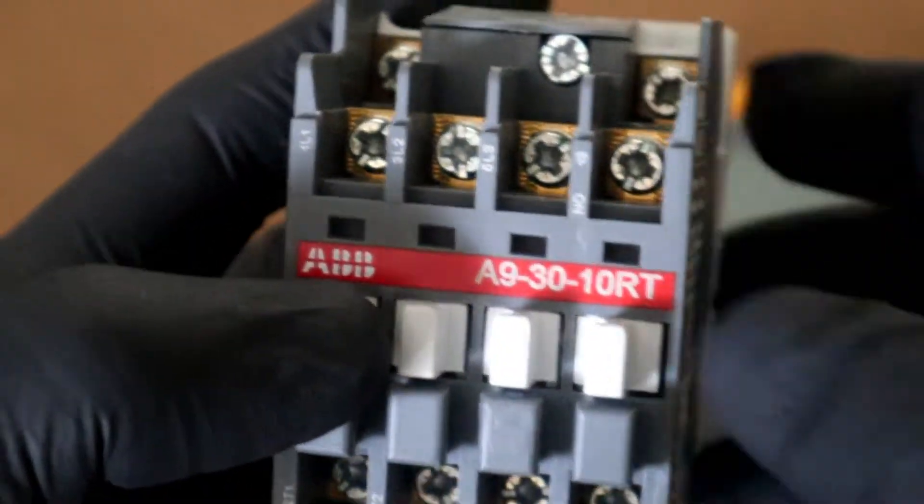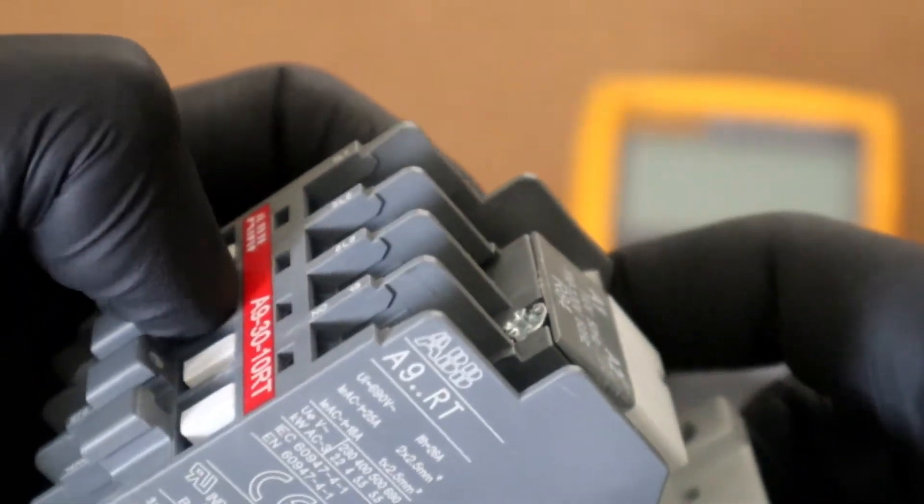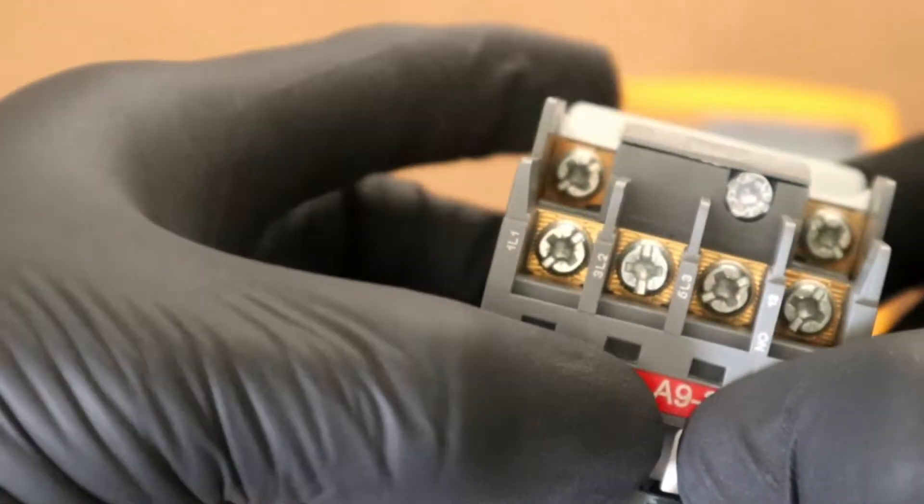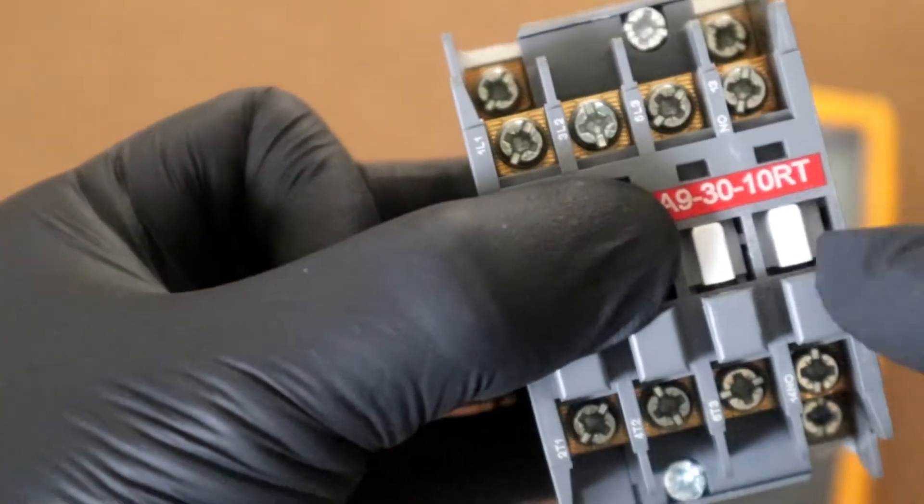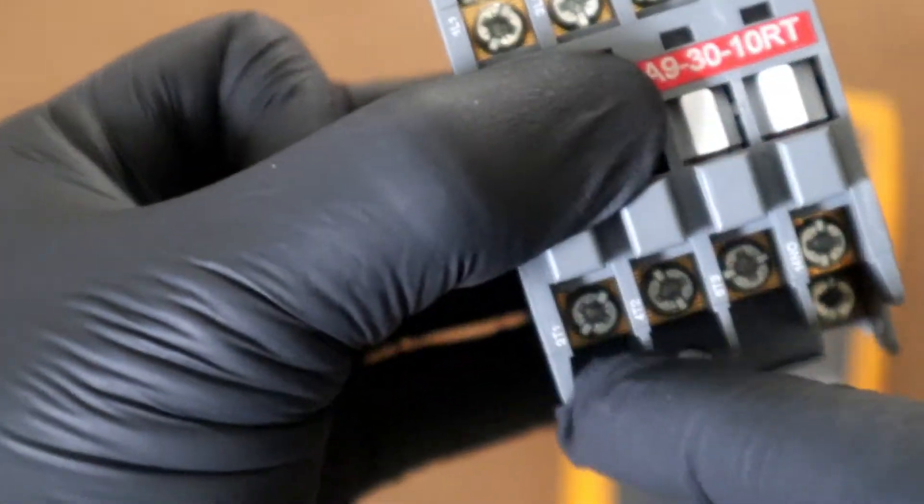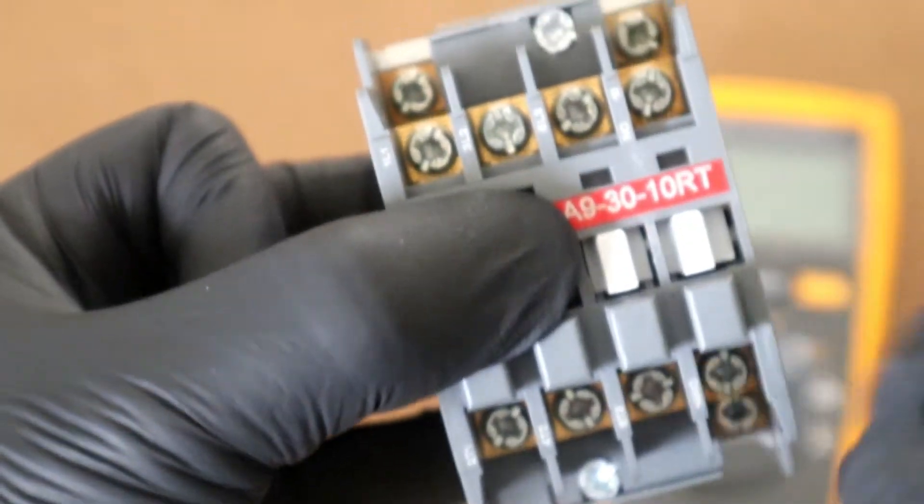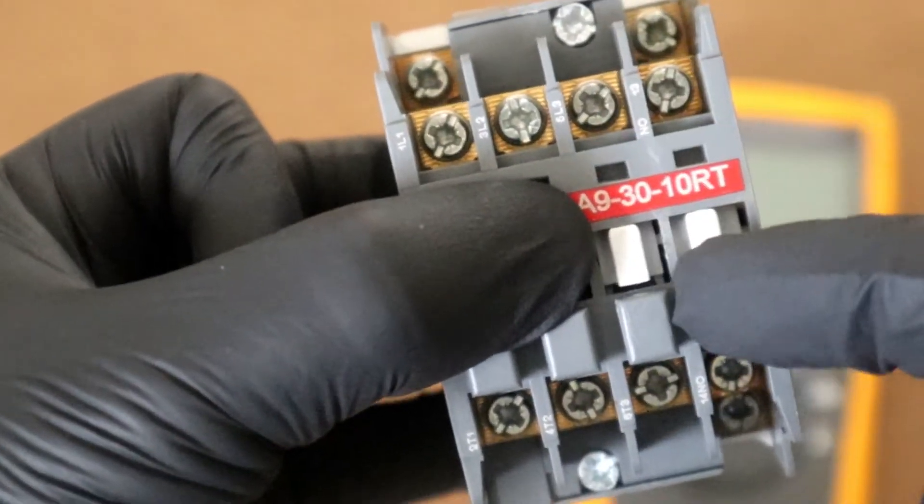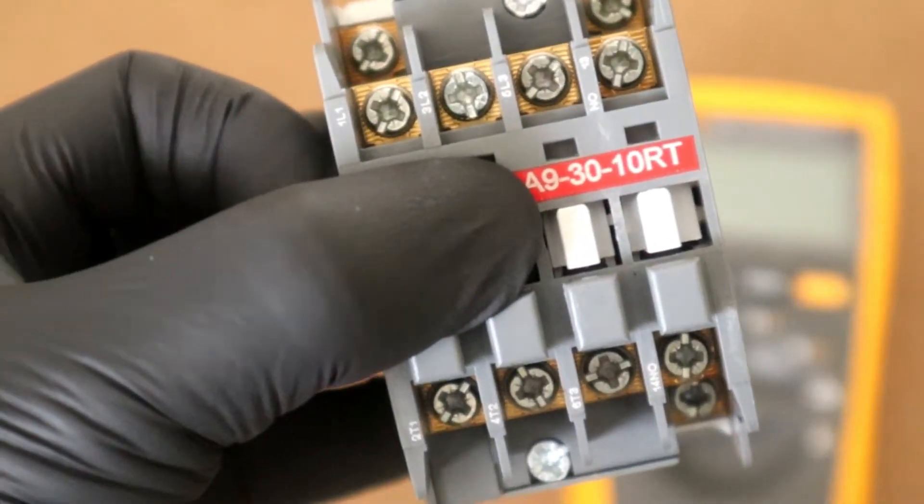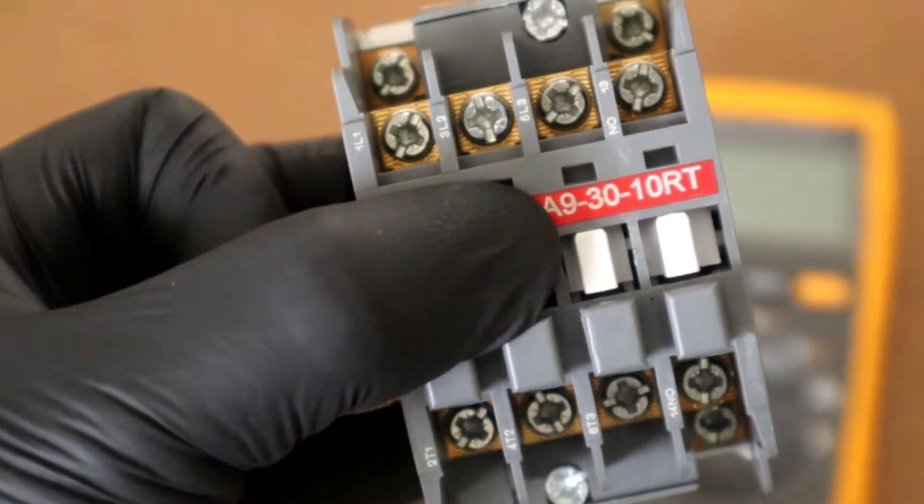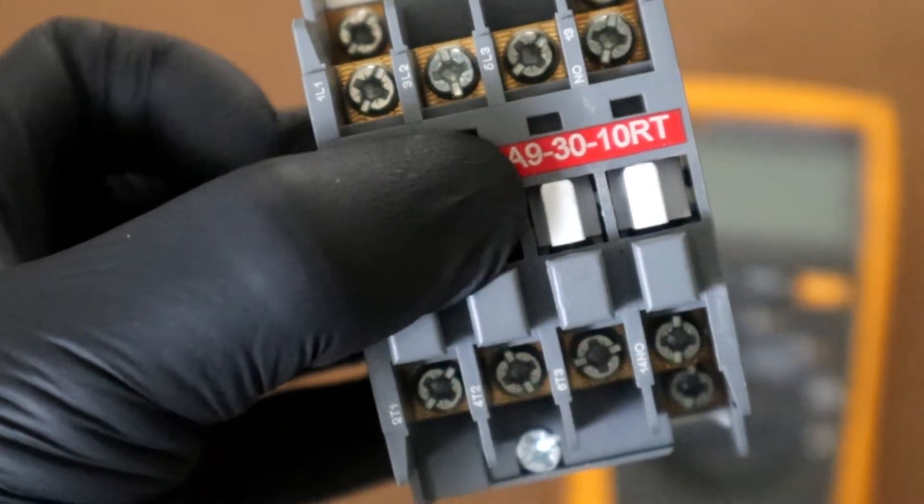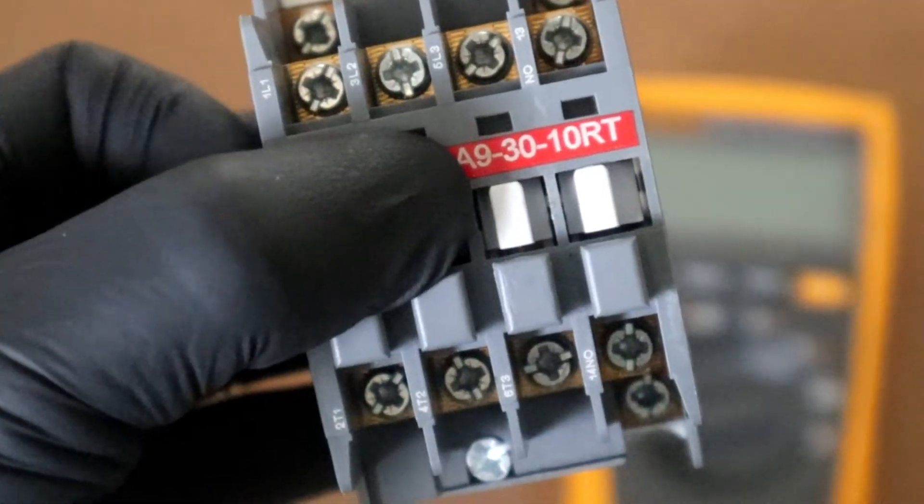On the contrary if we should press here with our fingers, simulating a closed contact, and go across L1 to T1, L2 to T2, L3 to T3 or across our normally open contact we should have a very low resistance reading, normally around 0.2 to 0.4 ohms.